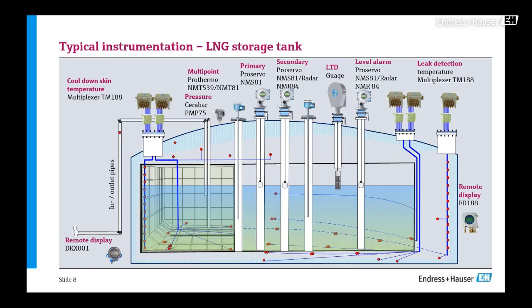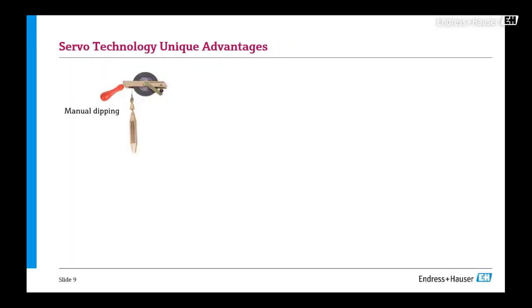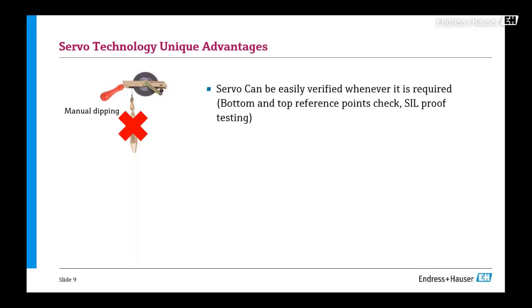And what are those advantages of the servo technology? In an LNG storage tank, manual dipping is something that you cannot do. And of course, if you don't have a way to verify the gauge, how are you going to do it? That is one of the advantages of this technology. A servo gauge can be easily verified whenever it's required. You can do a bottom and top reference check of this gauge. And of course, if you use it for your alarm, then you can also do a SIL proof testing anytime it is required. So this is one of the key advantages of this technology.